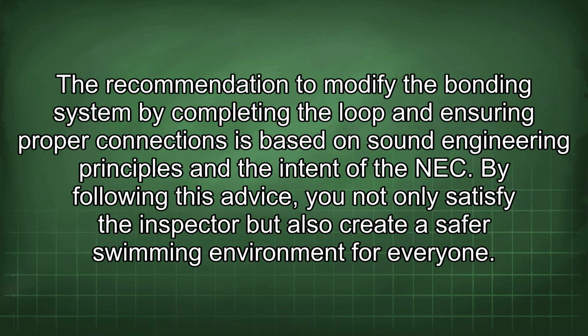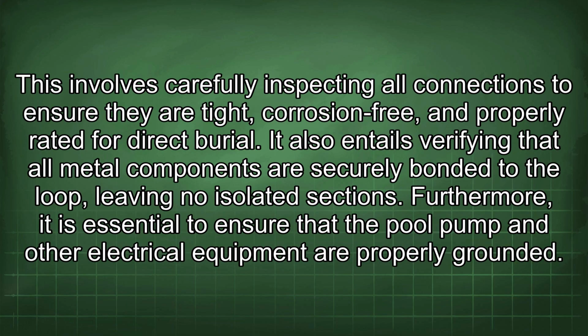The recommendation to modify the bonding system by completing the loop and ensuring proper connections is based on sound engineering principles and the intent of the NEC. By following this advice, you not only satisfy the inspector but also create a safer swimming environment for everyone. This involves carefully inspecting all connections to ensure they are tight, corrosion-free, and properly rated for direct burial. It also entails verifying that all metal components are securely bonded to the loop, leaving no isolated sections.